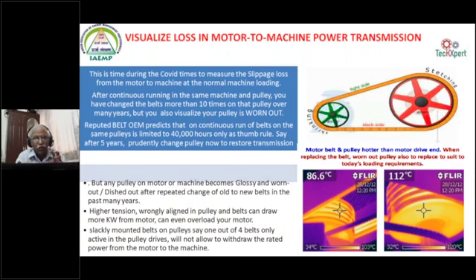So with a motor having a high tension pulley and belt, you can see the temperature on the pulley is almost 90 degrees and 112 degrees. This was taken in the year 2012 during our energy audits. What we learned from the energy audits, we wanted to share with industry professionals like you. Here, the belt and pulley temperature is higher than that of the motor, because it is over tensioned. If it is high tension, the motor goes into overload. If it is slackly tensioned, out of 4 belts only one belt is working, so a 50 HP motor will work for only 30 HP. It gets saturated at 30 HP because it is not able to transmit the power from the motor to the machine.